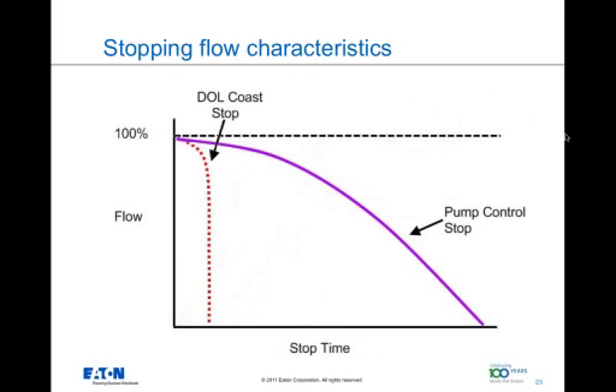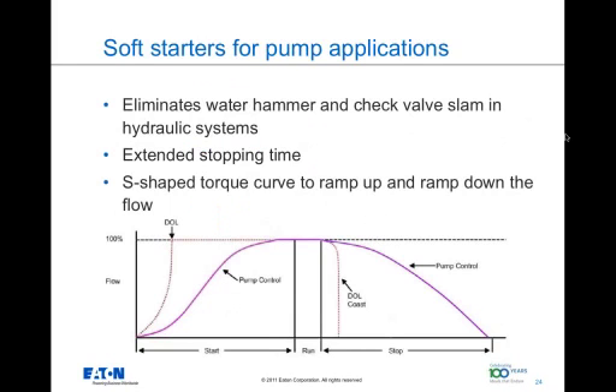Now let's look at the stopping characteristics in a pumping system. The DOL, which is direct online, reduces the flow quite rapidly. Pump control reduces sudden change in flow by controlling the deceleration of the pump motor and extending the time to get to 0% flow, thus minimizing check valve slamming. To summarize, this slide compares flow versus time when different starting and stopping techniques are employed. The soft starter with pump control option produces the most desirable flow characteristic when starting and stopping centrifugal pump motors. There are no sudden peaks or breaks in flow that result in surges or hammering or slamming in the system.